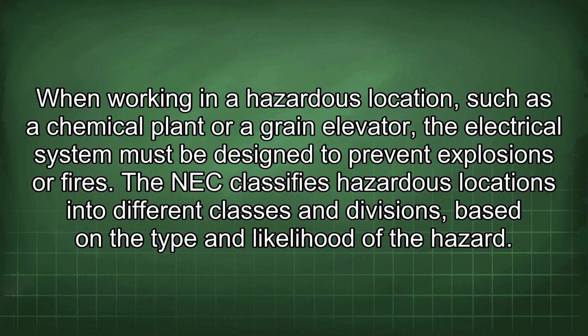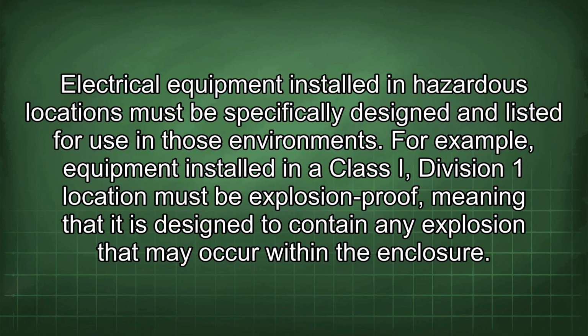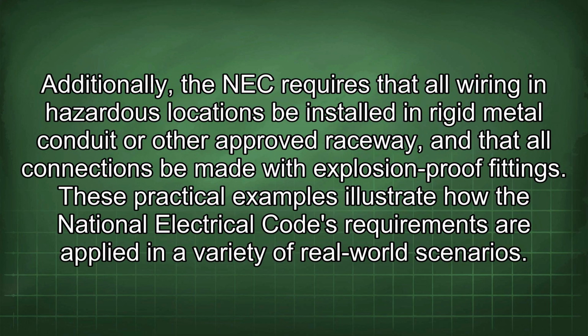When working in a hazardous location, such as a chemical plant or a grain elevator, the electrical system must be designed to prevent explosions or fires. The NEC classifies hazardous locations into different classes and divisions based on the type and likelihood of the hazard. Electrical equipment installed in hazardous locations must be specifically designed and listed for use in those environments. For example, equipment installed in a Class I Division 1 location must be explosion-proof, meaning that it is designed to contain any explosion that may occur within the enclosure. Additionally, the NEC requires that all wiring in hazardous locations be installed in rigid metal conduit or other approved raceway, and that all connections be made with explosion-proof fittings.